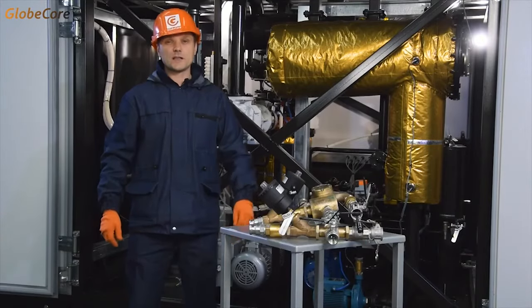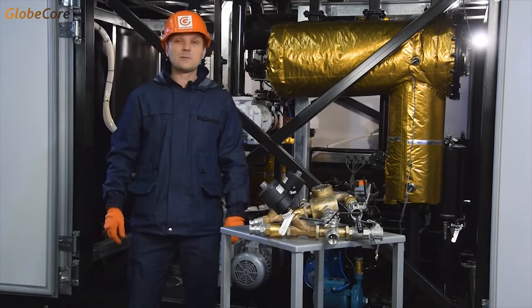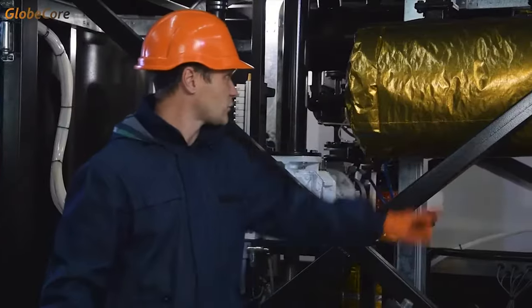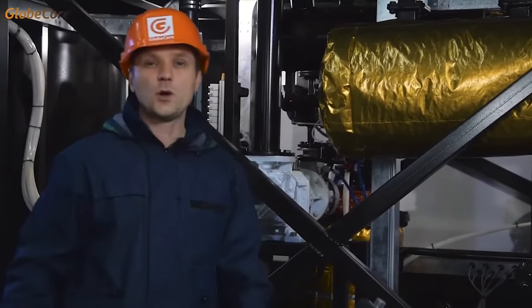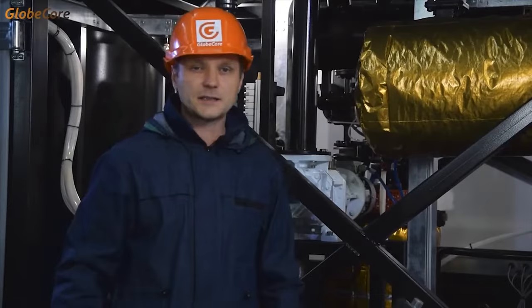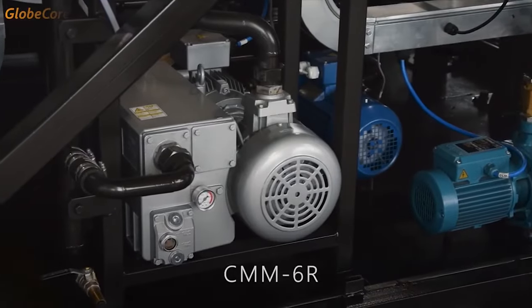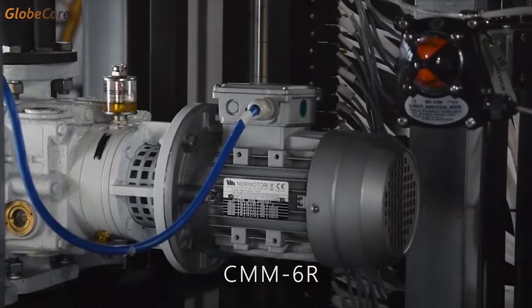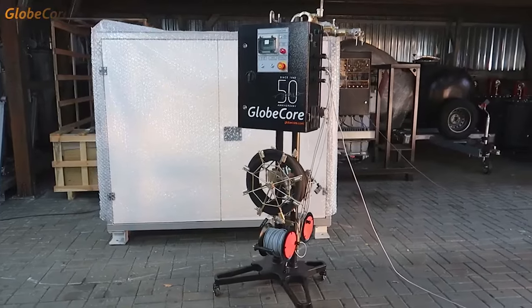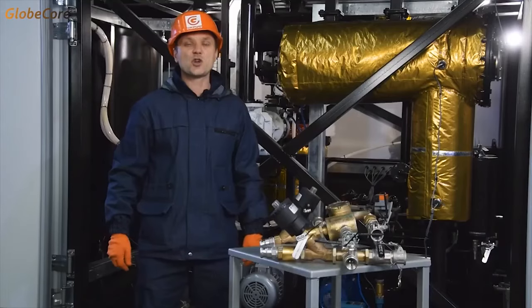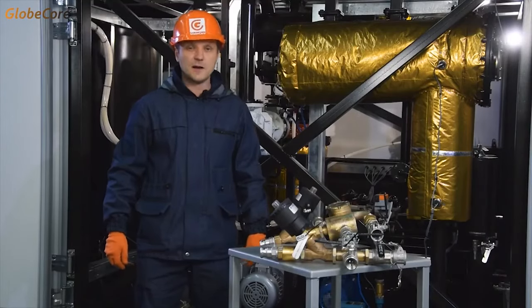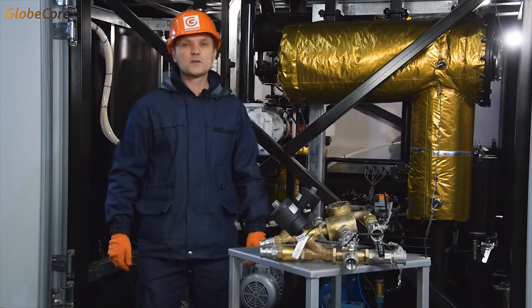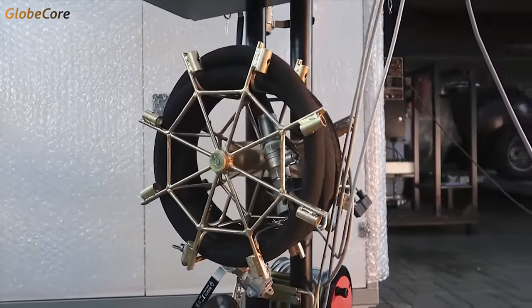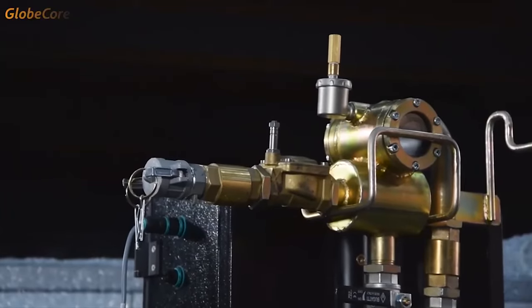Furthermore, we obviously need flawless quality of oil to return it to the transformer, which means that we cannot do without drying and degassing of the oil. This is performed by the plant's degassing section, which brings the humidity and gas content of regenerated oil to the specifications. Since it's very desirable to service a transformer without turning it off, the CMM-6R includes the TSS module, a transformer safety system, which ensures reliable transformer operation during oil processing. The function of the TSS is to monitor and control the level of oil in the transformer. You will find more information on the TSS system in its own dedicated video.